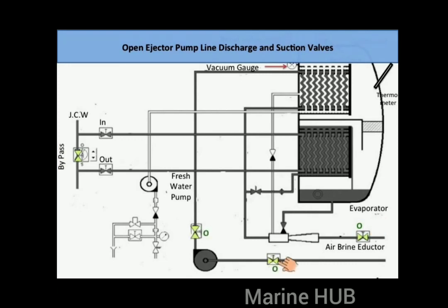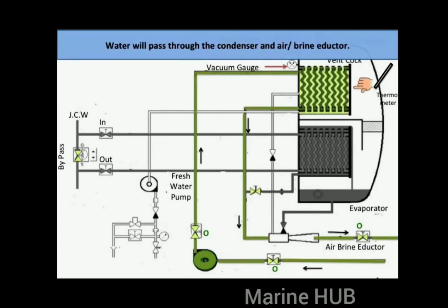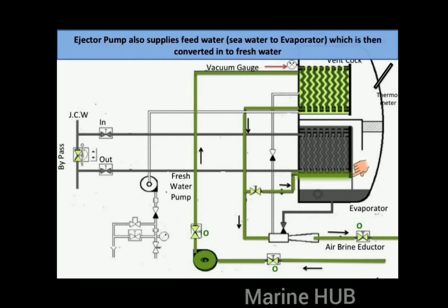Open the ejector pump discharge and suction valves. Open the feed water valve to the fresh water generator evaporator, then start the ejector pump. Water will pass through the condenser and the air brine eductor. The ejector pump also supplies feed water to the evaporator, which is then converted into fresh water.